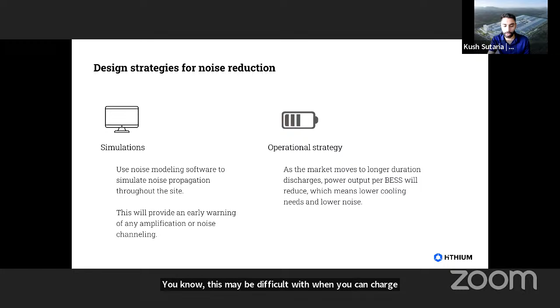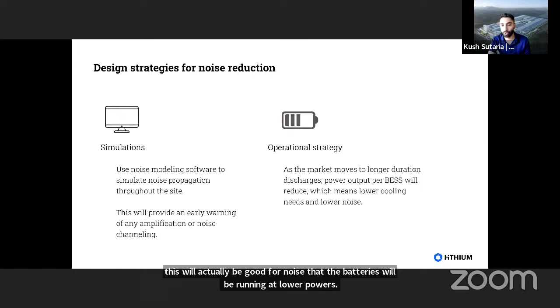Also, where possible, adjust your operational strategy, though this may be difficult given when you can charge and discharge. As the industry moves to longer and longer durations, this will actually be good for noise, since the batteries will be running at lower powers, meaning they need less cooling, which translates into less noise. For us at Hithium, we're building our next generation 6.25 megawatt hour container for long duration. That has a lot of benefits, but in terms of noise, it means we can use a smaller cooling system that takes up less power, which helps reduce noise.